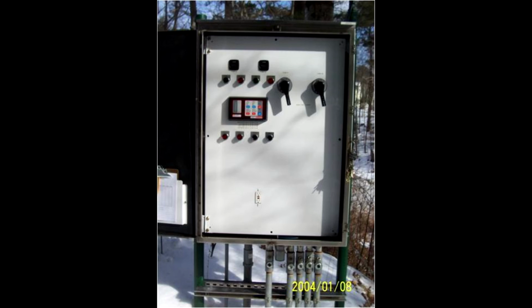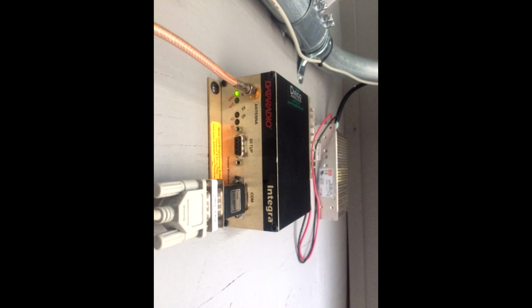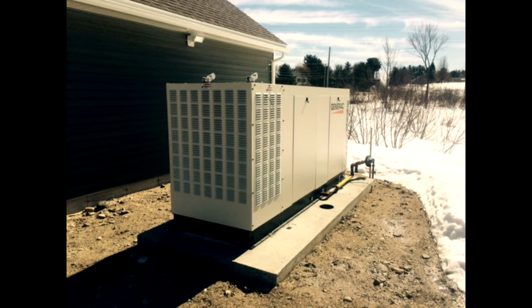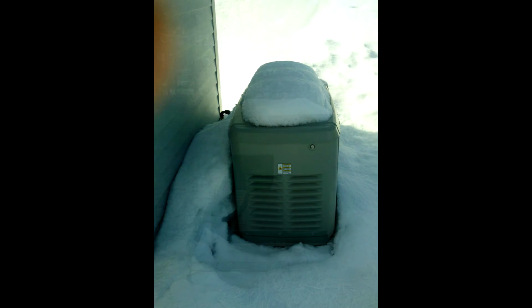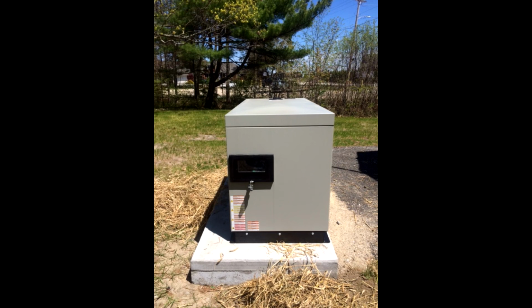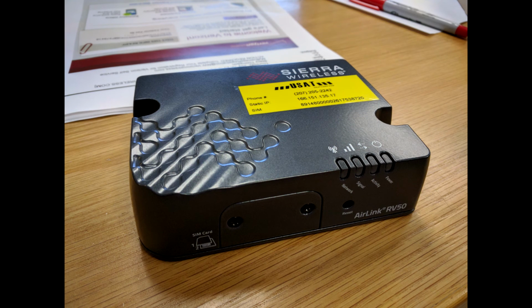All stations communicate back to the plant via radio telemetry and send alarms if there is a trip pump, low level, high level, loss of communication, or if the generator has come on. 16 of the pump stations do have an on-site generator which transfers power automatically if there's a power outage. We have 3 portable generators for the stations without a backup generator in case of emergency. Currently, Saco is going through an upgrade of the last CAN pump station and also converting from radio telemetry to wireless communication.